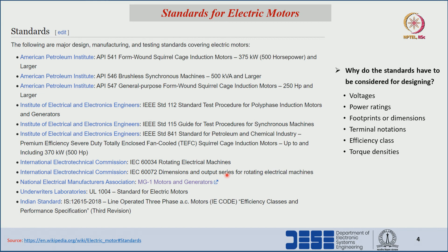Why must we follow standards? With respect to available voltage ratings — 230 volts single-phase, 440 volts three-phase, 11 kV or 33 kV depending on the utility grid side — standards define what voltage ratings, power ratings, footprints or dimensions, terminal notations, efficiency class, and torque densities are permissible. Standards provide a generalized, common approach for all manufacturers so that maintenance and analysis will be easy for all types of machines.